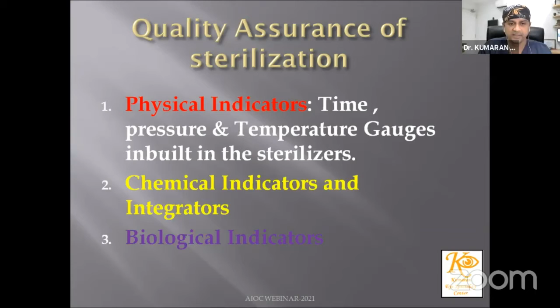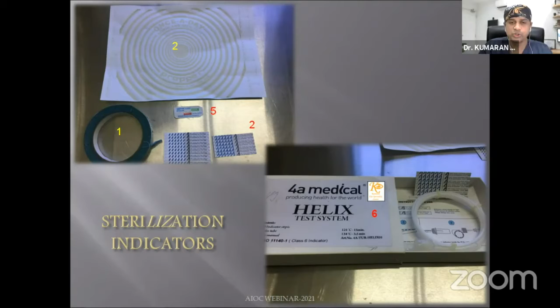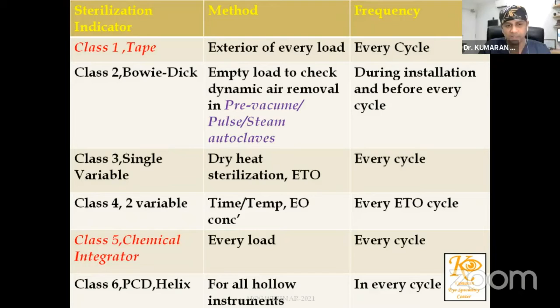Then whatever autoclaving you've done, quality assurance of sterilization is very important. There are 3 basic parameters: the physical indicators, chemical indicators, and the biological indicators. These are all the indicators which have to be used to make sure that your sterilization process is effective. This is a small tabular column I have listed of how frequently one has to use all these indicators. There is no clear consensus of how frequently they should be used. We basically follow the American standards where every cycle has to be done with these indicators.